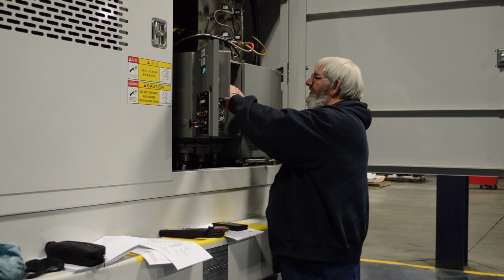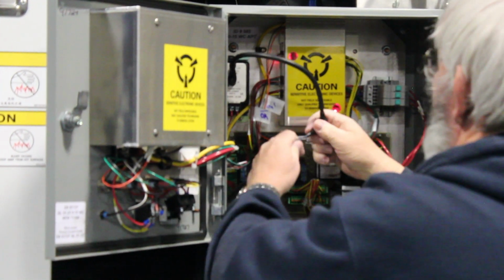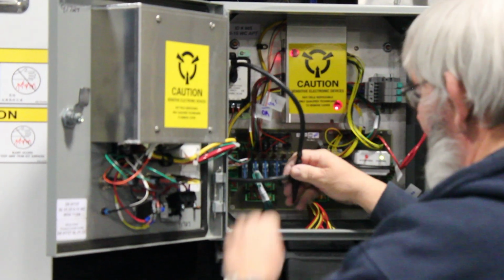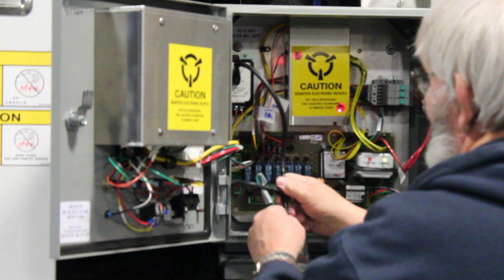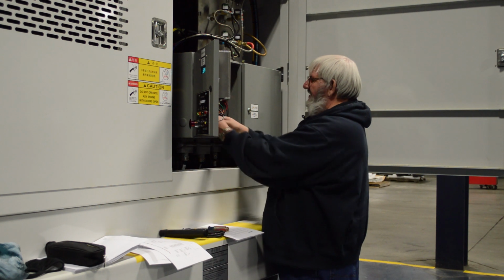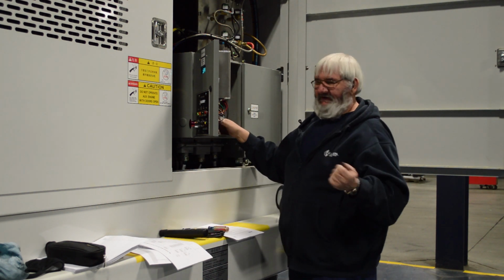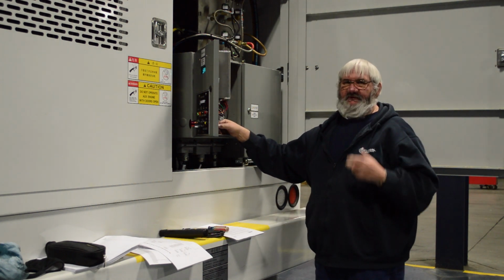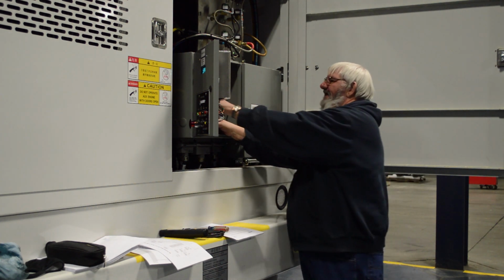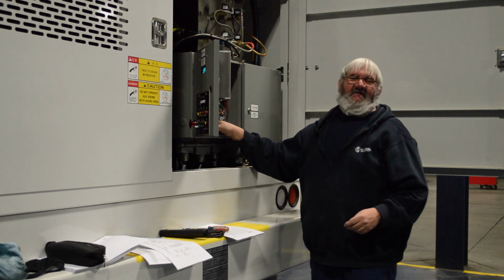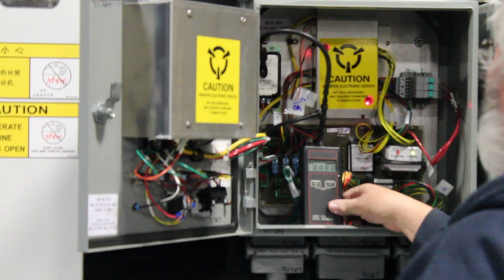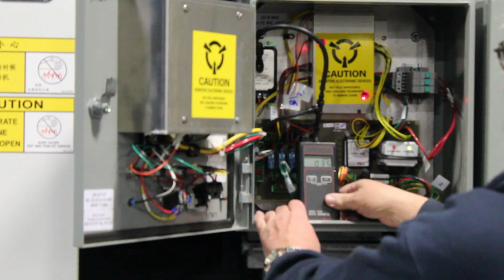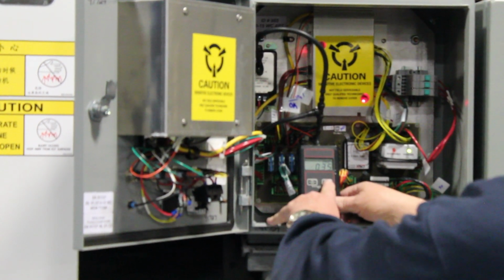Simply hooking up your jumper hoses, feed line from the heater, and then our connection point to our manometer. But basically what you would be looking for at this point is to see if your air pressure transducer is reading the same as your manometer. Keep in mind your manometer is just a testing device. So you would turn it on. Zero it out.